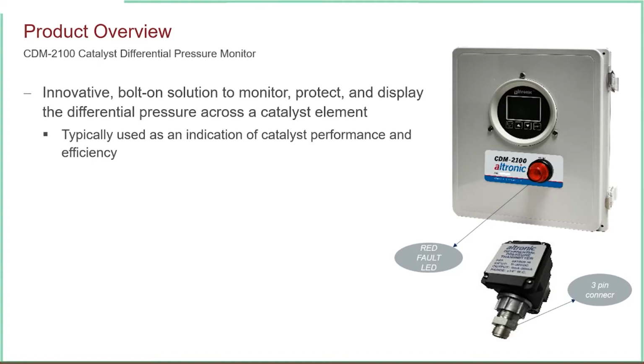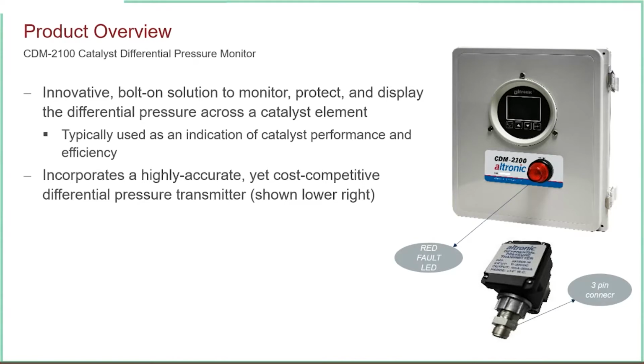Basically, the idea was an innovative bolt-on solution to monitor, protect, and display the differential pressure across any of the catalysts on these big engines. That's typically used as an indication of the catalyst performance and the efficiency. You can see in the bottom right-hand corner the actual DP transducer that we'll be using. It's essentially negative 14-inch water column to positive 14-inch water column, so 1 pound across the spectrum. We'll get into a little more as we go through the slides.